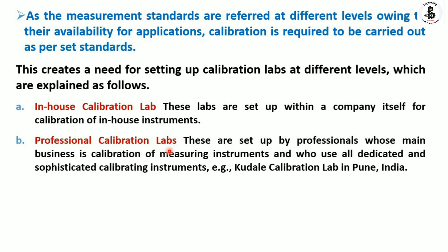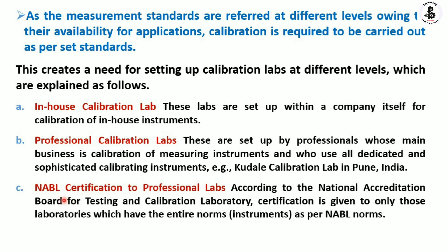Secondly, professional calibration labs. These labs are run by professionals whose main business is calibration of measuring instruments, and who use dedicated as well as sophisticated calibrating instruments. In India, the Kudale calibration lab in Pune is an example of a professional calibration lab. These professional labs also carry the NABL certification — according to the National Accreditation Board for Testing and Calibration Laboratories, a certificate is given to only those laboratories which meet all the norms as per NABL standards.